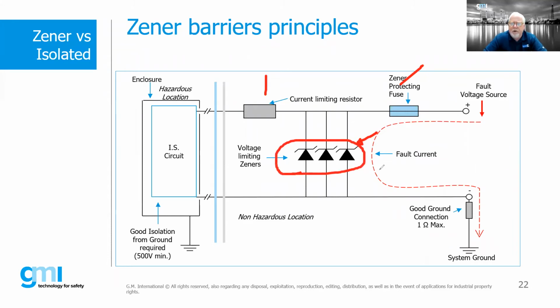Just by looking at this drawing, I know this particular Zener barrier is suitable for Zone 0. It's an IA barrier because it has redundancy, and that's a requirement. If it only had 2 Zener diodes, we'd know this barrier's circuitry is an IB circuit. If it had a single one, it would be an IC circuit. But it's basically set up in this fashion.